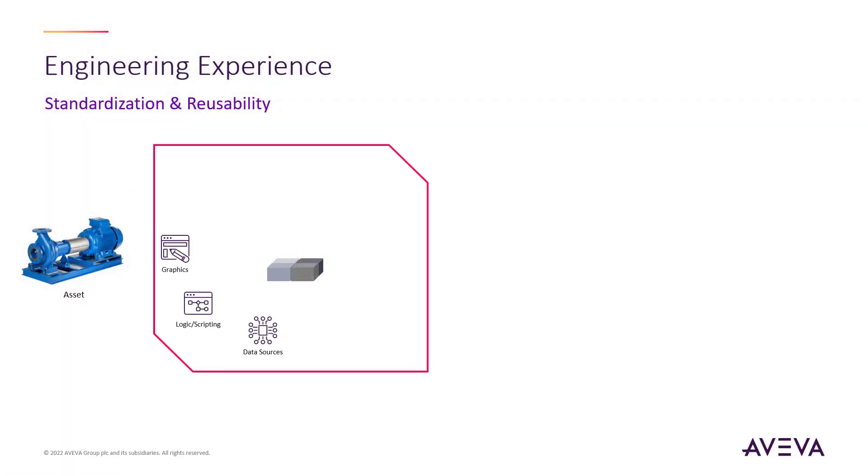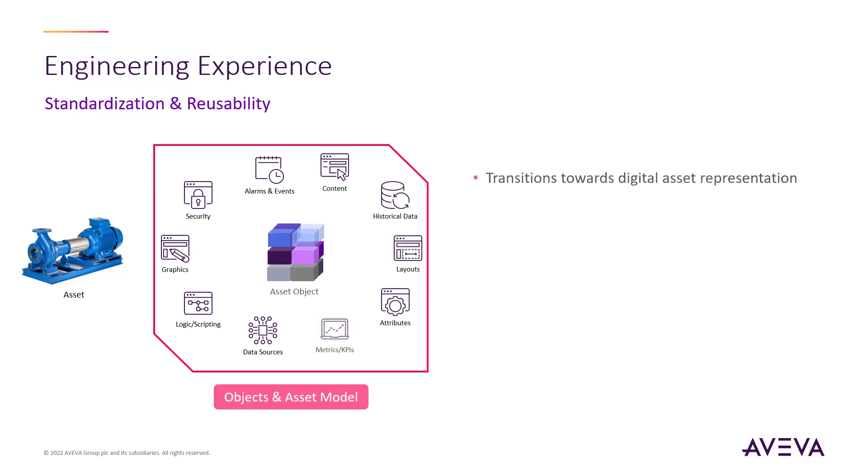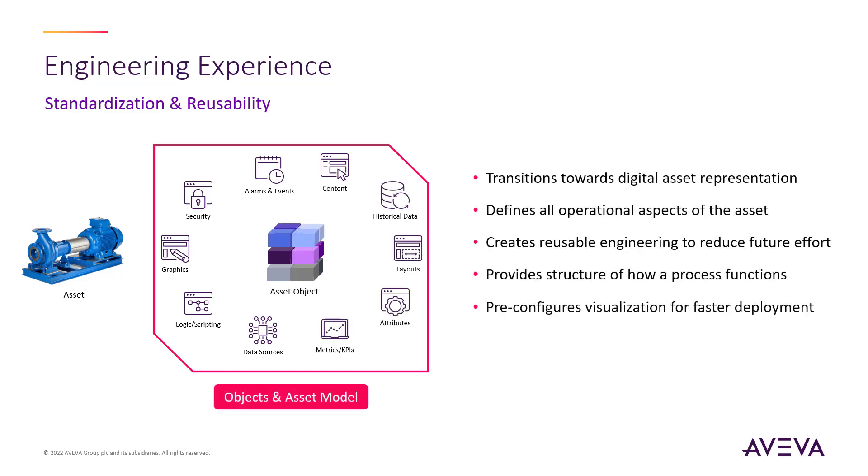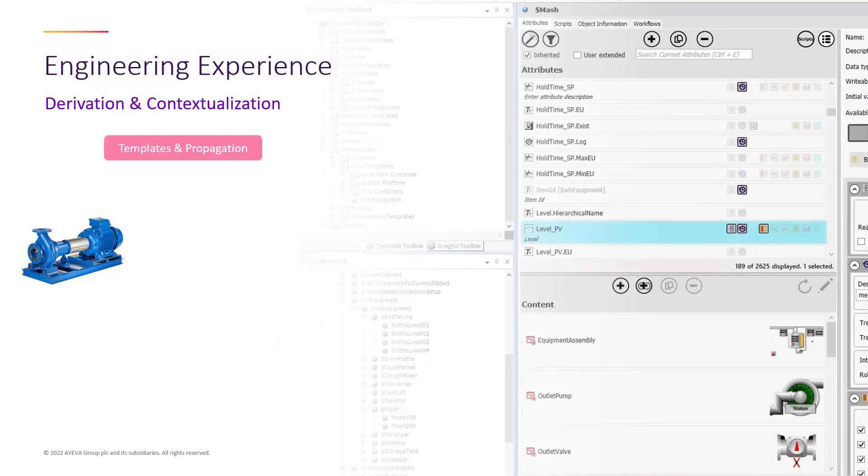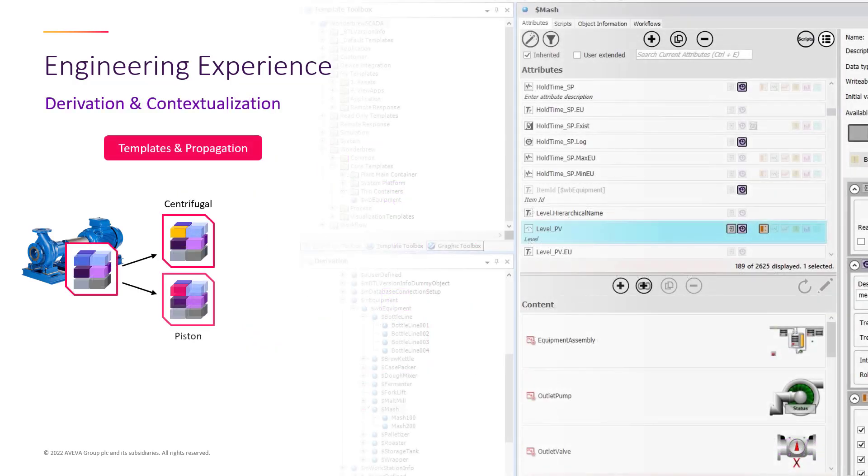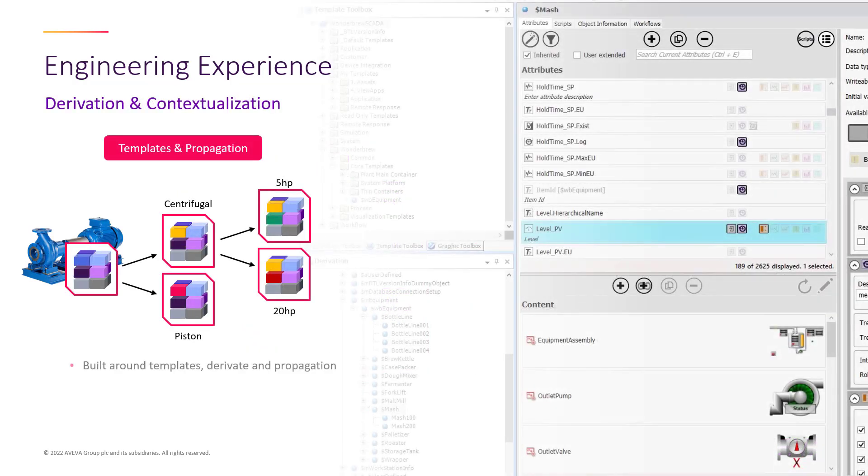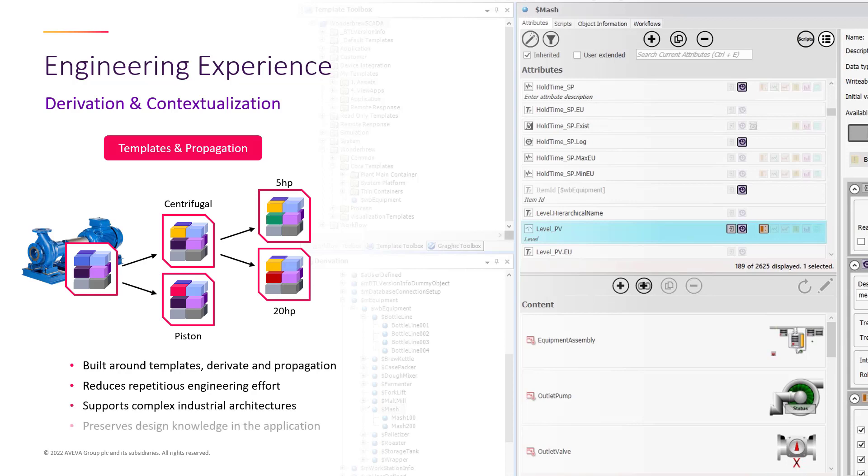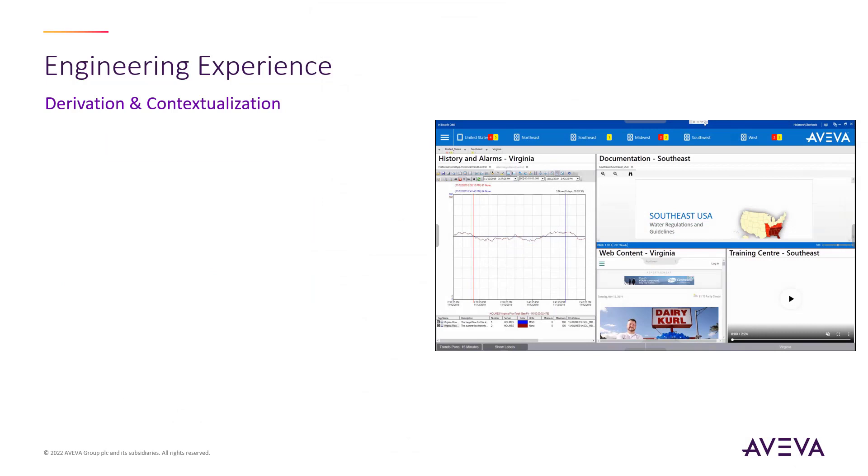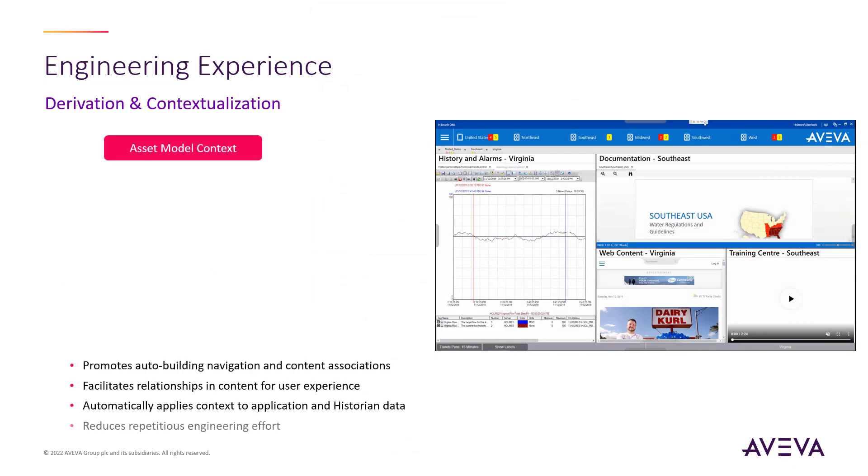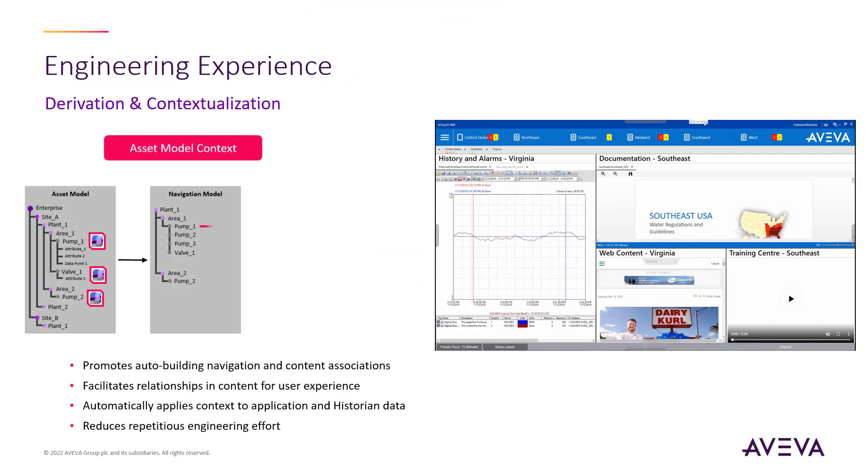The ability to derive objects takes advantage of encapsulation and inheritance in the relationship between parent and child. When an object is derived from a template, that child object will inherit all components from the parent object, including attributes, graphics, security, scripting, and more. This has many benefits for usability and standardization because any modification made in the parent object will automatically propagate to all derived child objects.